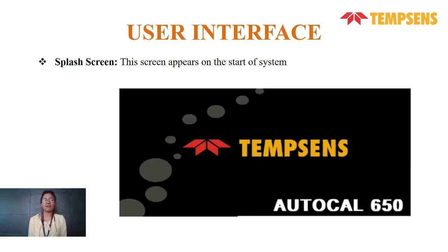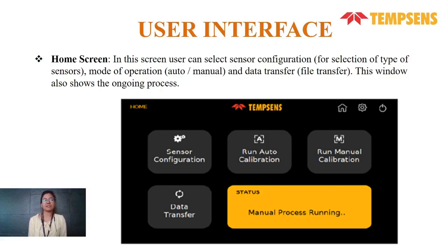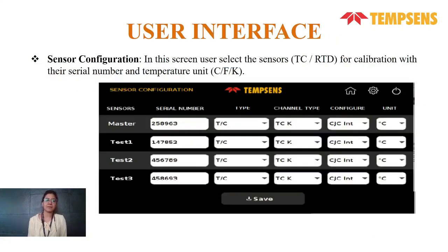When we operate our automatic temperature calibrator, the home screen will appear on our LCD display. Here we can select many options like sensor configuration, run auto calibration, run manual calibration, and data transfer. The status bar shows the furnace running process, meaning the ongoing process of our furnace.